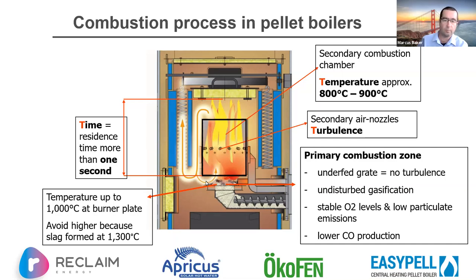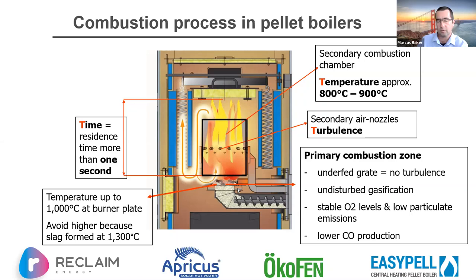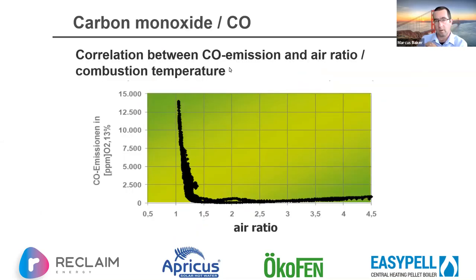We get quite high temperatures down at the bottom in the primary area, but we've got to be careful — especially in New Zealand — because we've got very high silica content in a lot of our pellets. They still meet international standards but tend to have quite high content due to our volcanic soils. We don't want temperatures above 1,200 to 1,300 degrees here because you get slag formation, which occurs if there's not enough air and combustion products are not being moved through the system.